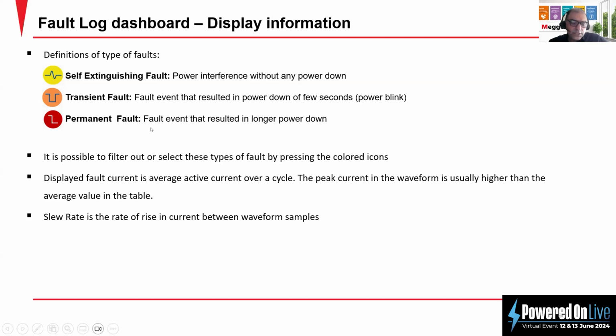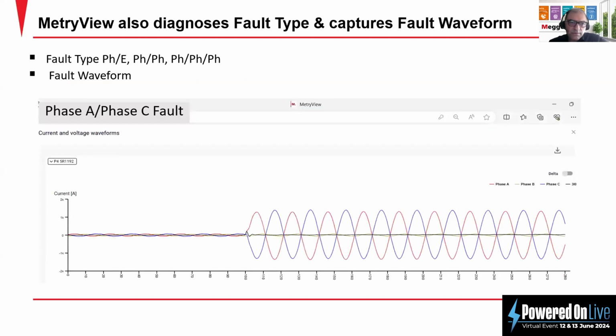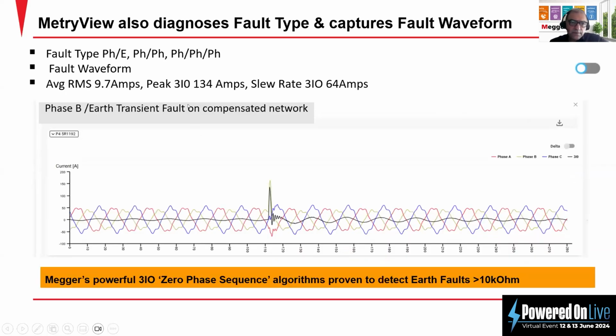and the slew rate of each fault will be shown, and all the current, average and peak current information of each fault with the waveform will be shown in the software. This is an example of a fault. It shows the type of the fault, like phase-to-phase and three-phase fault, showing the waveforms of the fault. For example, this one is between phase A and C. Another example of a fault is a phase-to-earth fault, and it's a transient fault.